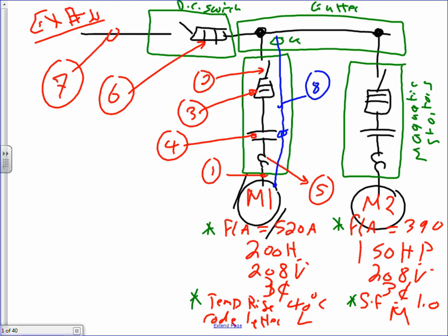As a matter of fact, if you guys adjust this one to make it more appropriate, I want to adjust this particular one, the 7. 7 should be coming directly from here, really, technically. 7 is the feeder, right in here. This is where 7 is. Can you guys adjust this one, the cable? Because it doesn't do you any good to have the cable ahead of the overcurrent protection box. Okay?